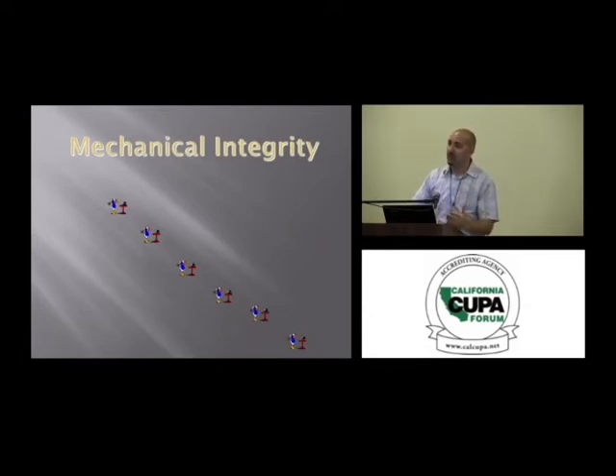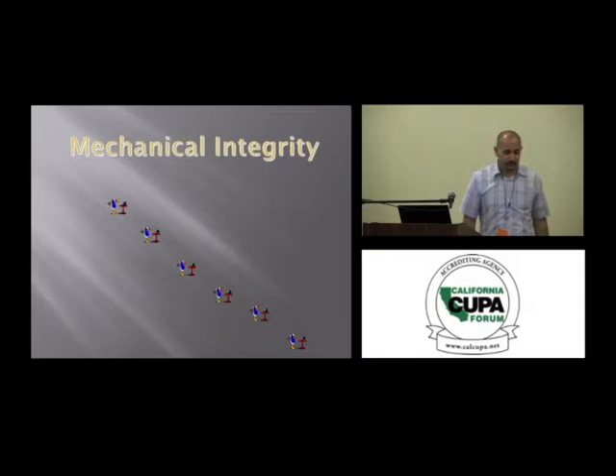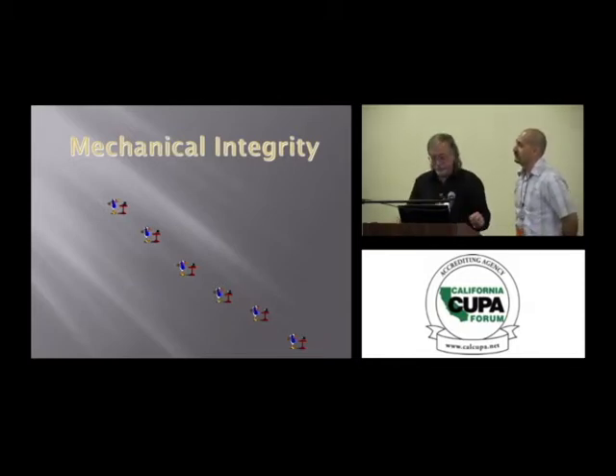When it does pop off, you will definitely have less ammonia leaving your system. I've seen relief valves that are sized 10 times the size of what needs to be on there. You release ammonia, what it should be by the pressure vessel code per the size of the vessel. Now you multiply that by 10 times, it's a 10-time headache. Are they cheaper this smaller? Pretty much the same price. Yeah, they're the same price.